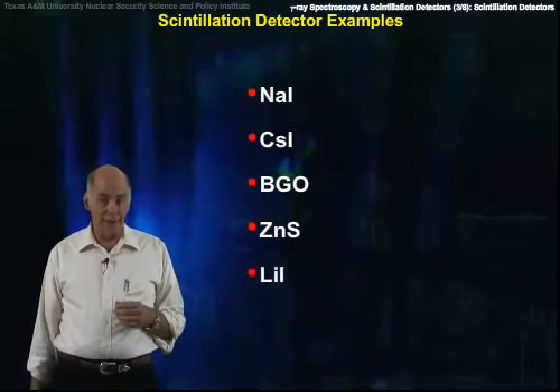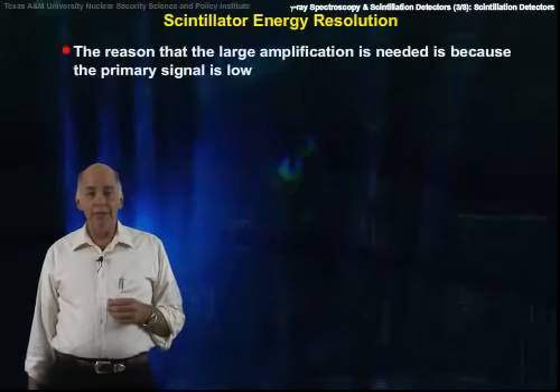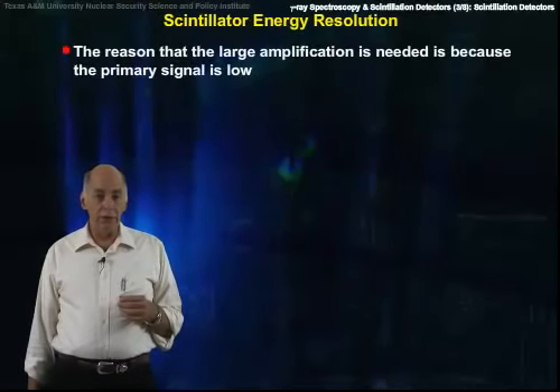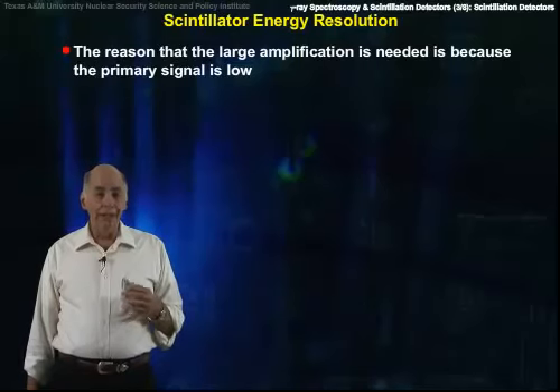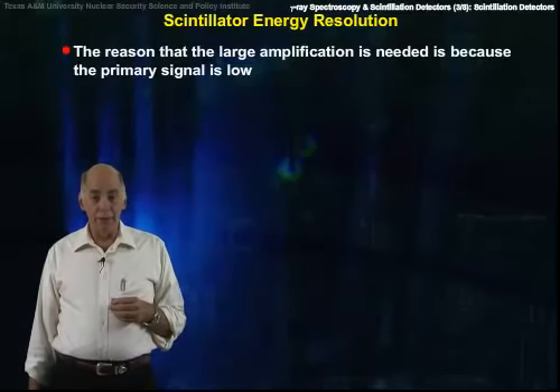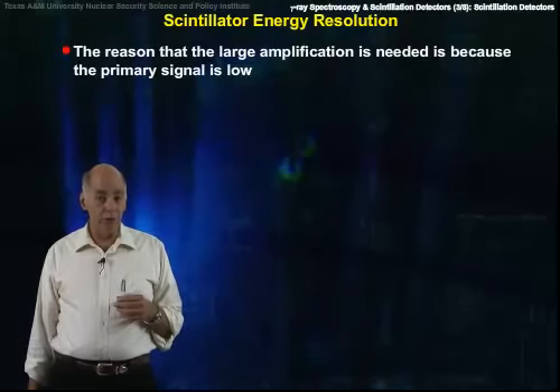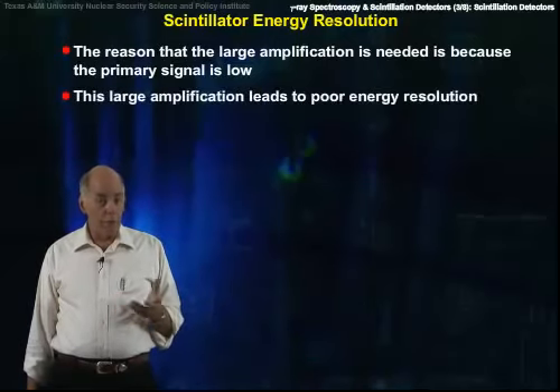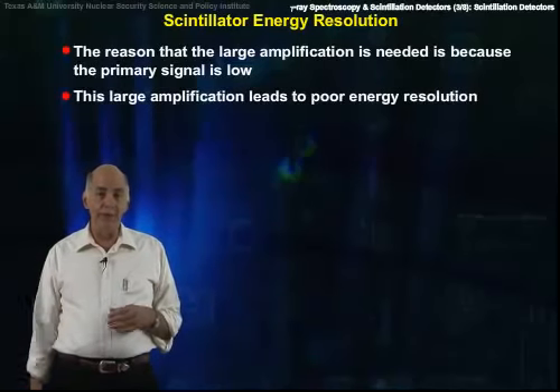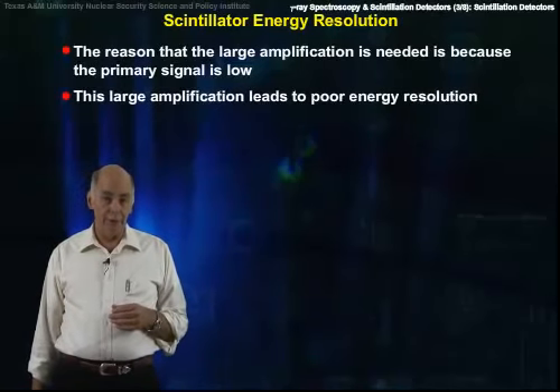a neutron detector. The main reason that photomultiplier tubes are needed is that we need a large amplification because the primary signal out of the scintillation material is low. Unfortunately, this large amplification leads to poor energy resolution.